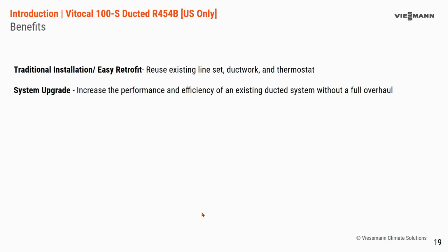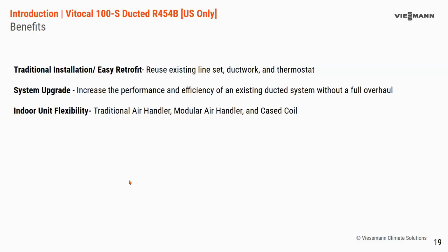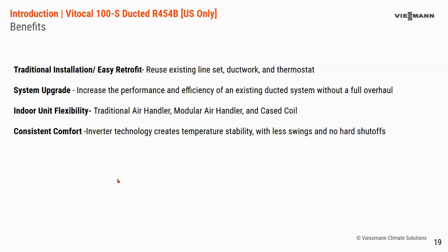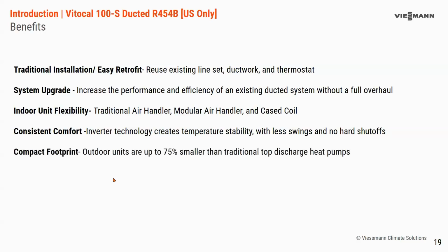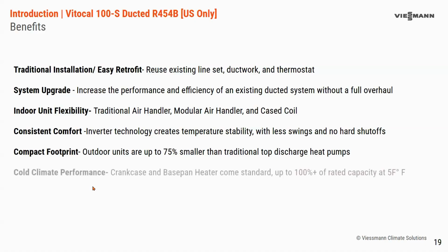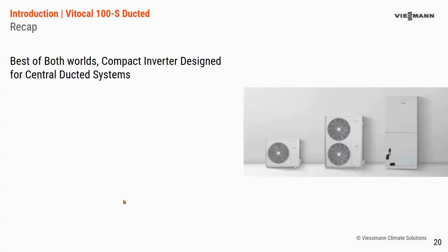So benefits: traditional installation, so familiar, you can reuse your line sets, ductwork, thermostat, but you can provide an upgrade of performance and efficiency to an existing system. You have the flexibility of the different indoor unit choices, but you're still able to provide the consistent comfort from the inverter technology. So soft starts, less temperature swings, better energy savings, while achieving footprint reduction at the outdoor unit as well. The cold climate performance is there, especially for the high heat. So the crankcase and base pan heater is still present on the regular standard heat, but doesn't have the full capacity at 5F like the high heat.